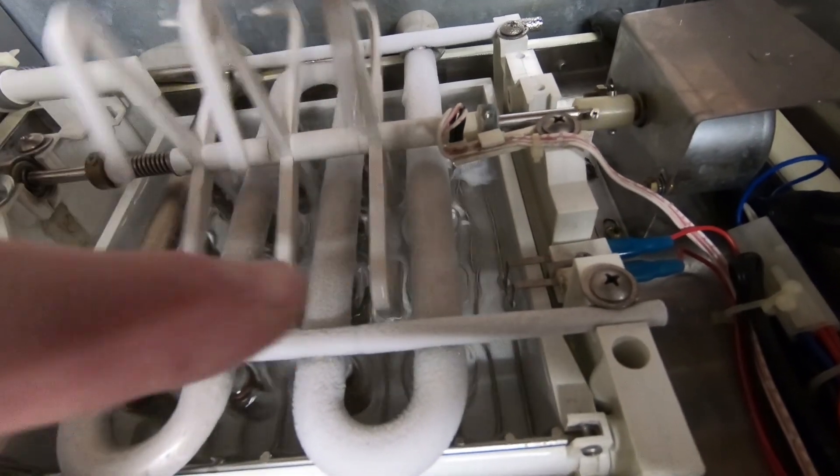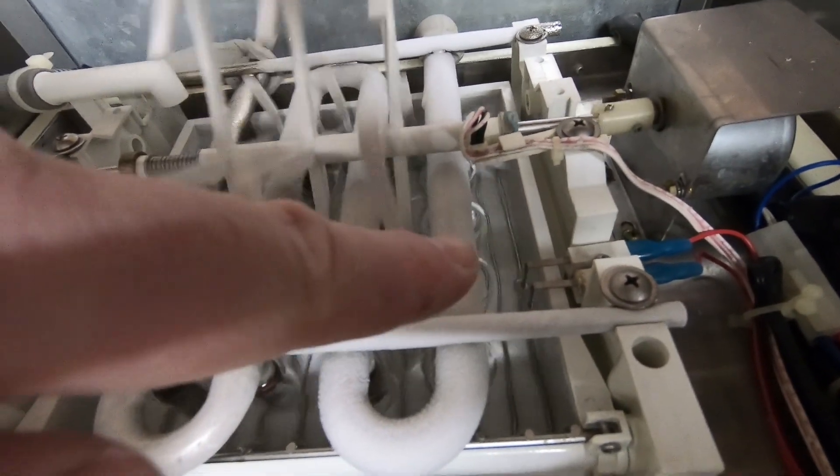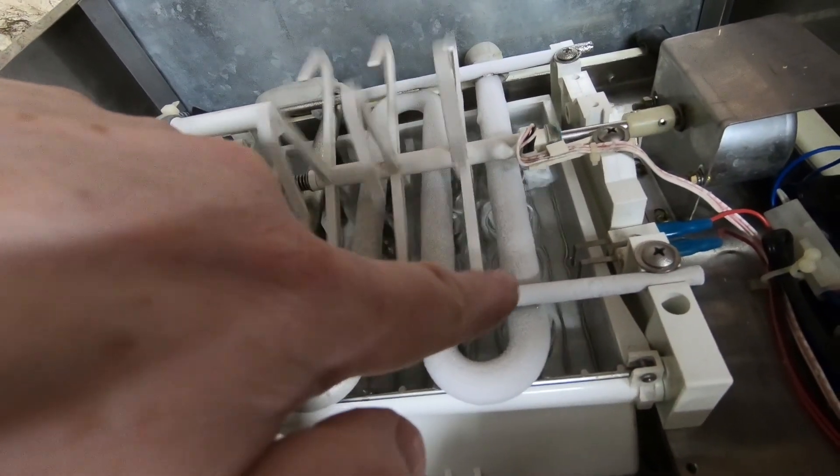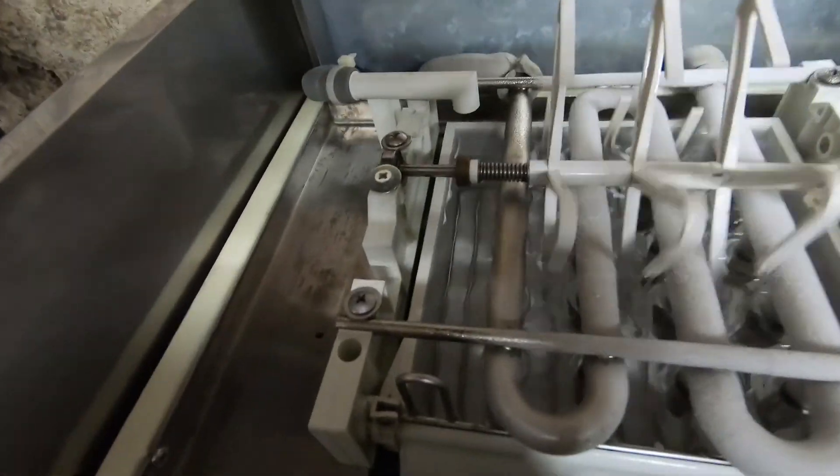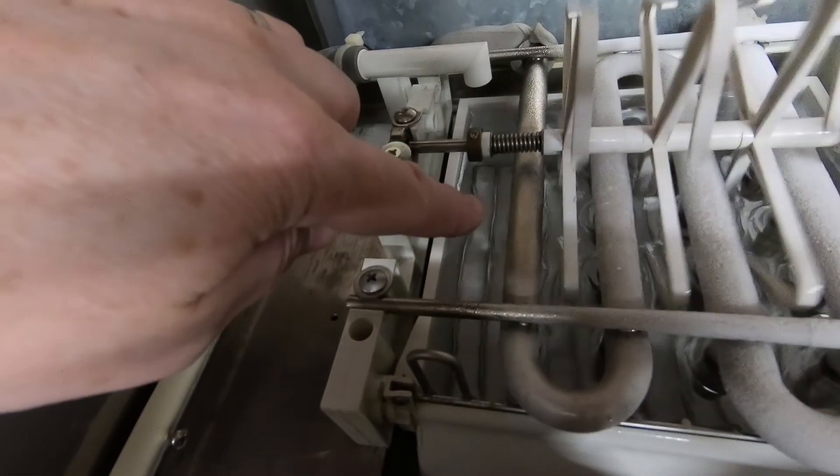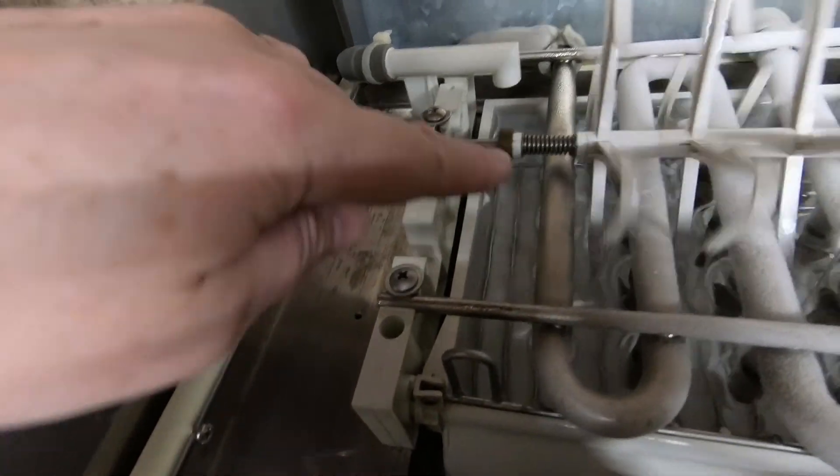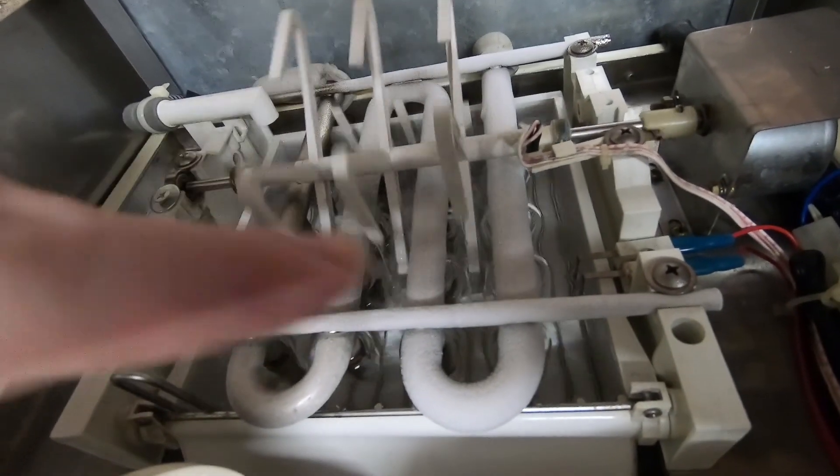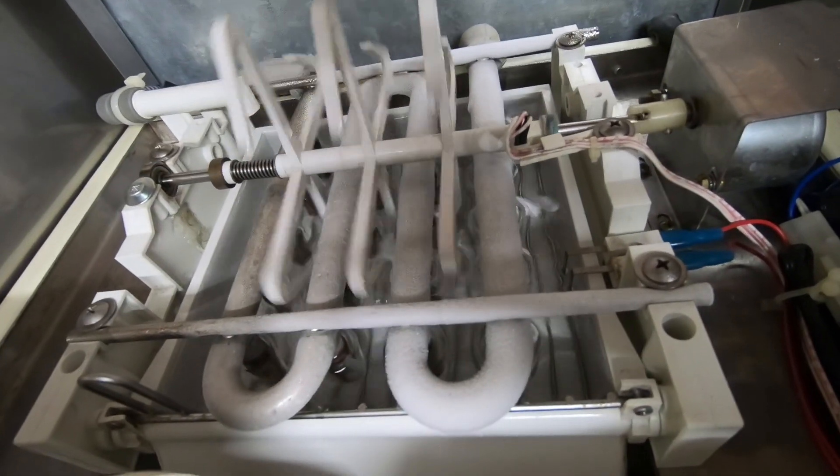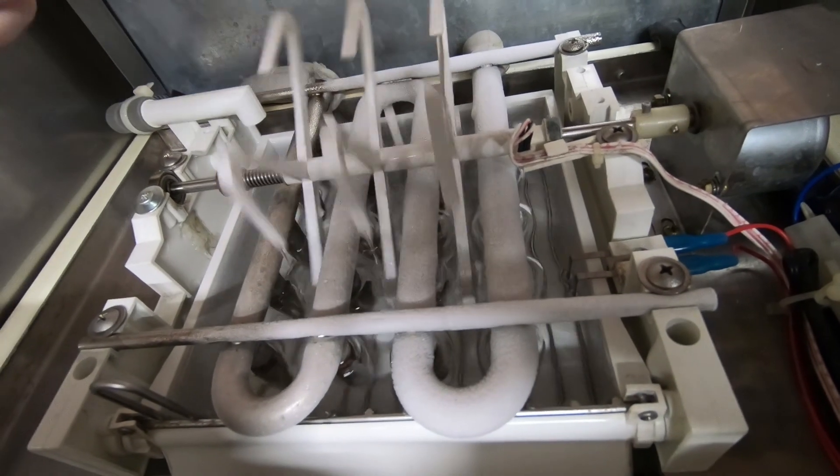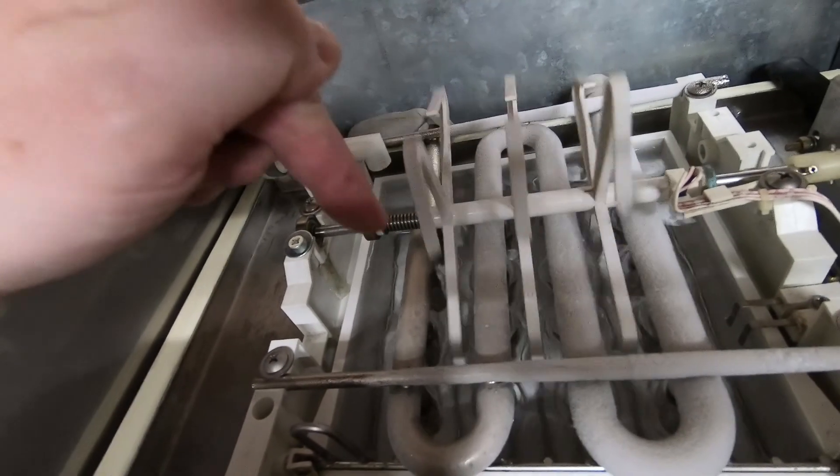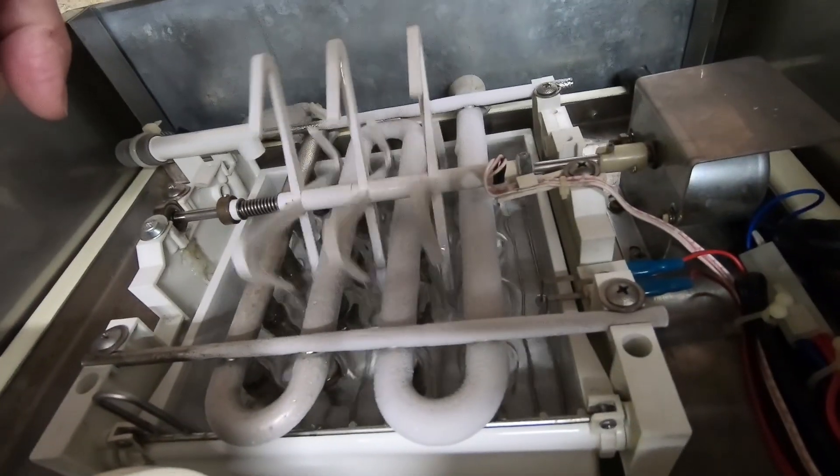Because this side always gets colder first, the ice always builds up to a bigger size on this side than it does on this side. You can see that there's not as much ice formed here. Now they do produce ice on this side, but it's always larger on this side. I think it might have been a better idea if you just had one of these detecting the size of the ice, perhaps on this side. That's how it works.